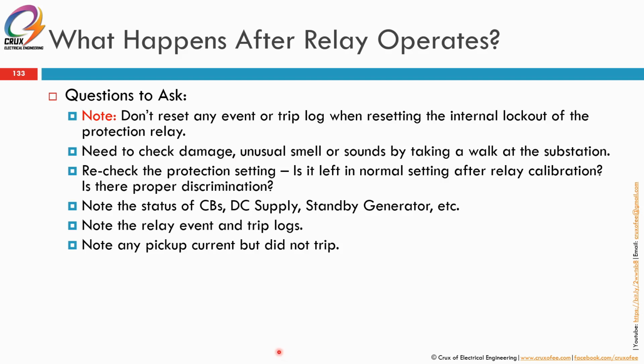You will also need to note any pickup current that did not trip. For this you might need to refer to other upstream relays. For example, maybe the motor tripped, but you also need to see whether the upstream breaker's relay also picked up any current during that fault. Sometimes it will assist us in identifying and troubleshooting the cause of the fault.